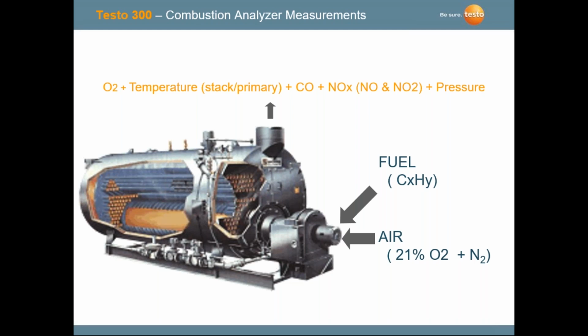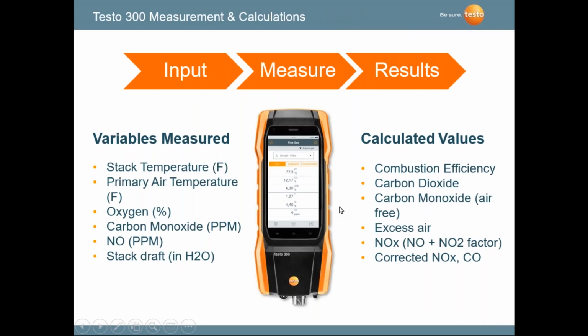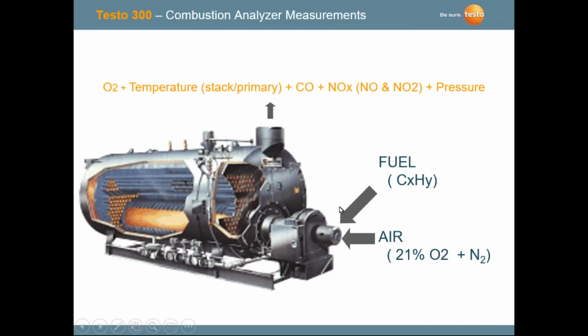where we're bringing in a hydrocarbon fuel, and we're bringing in air, which we all know is 21% oxygen and a balance of nitrogen. And what we're looking at: we're pulling a sample from the stack gases into the analyzer, and we're looking at the O2 measurement, the oxygen measurement in the stack gases. We're looking at the temperature measurement, both the stack temperature through a thermocouple and also the primary air temperature.